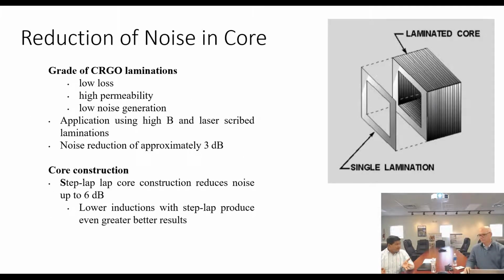The grades of CRGO lamination, as I explained to you earlier, which are used to make the core, have properties such as low losses, high permeability, and low noise generation from the core. When applied at higher flux density, or B, and with laser scribe lamination and high quality lamination cuts, it is possible to reduce the transformer's noise by 3 dB. Core construction also plays an important role in noise generation. Studies show that step lap core construction reduces the transformer noise by up to 6 dB, and at lower induction with the step lap, even greater noise reduction can be achieved.